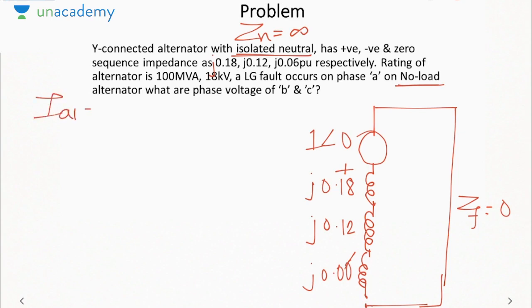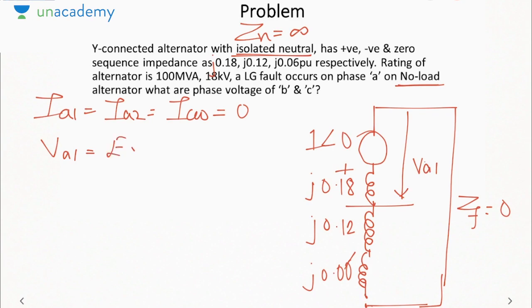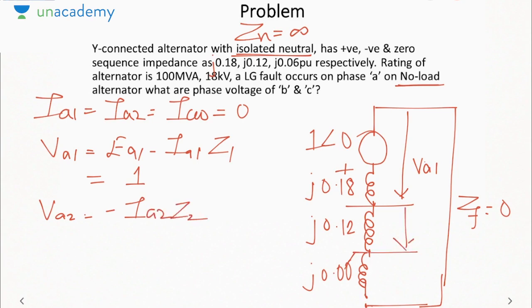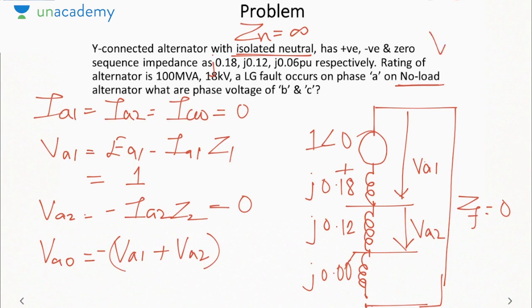Now here, since it is open circuited, all the sequence currents will be 0, due to which the positive sequence voltage VA1 is actually EA1 minus IA1 into Z1 will be equal to 1 angle 0. VA2 is actually minus IA2 into Z2. This will also be 0. Now VA0, we know since A phase is faulted, because VA1 plus VA0 plus VA2 must be 0. In case of LG fault, VA is equal to IA into ZF, but here ZF is 0, so VA must be 0. Hence VA0 plus VA1 plus VA2 must be 0. So VA0 must be minus 1.